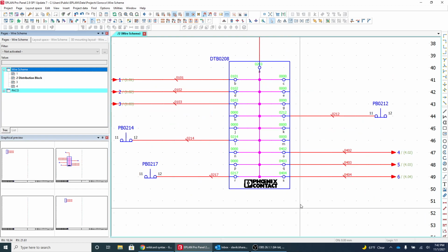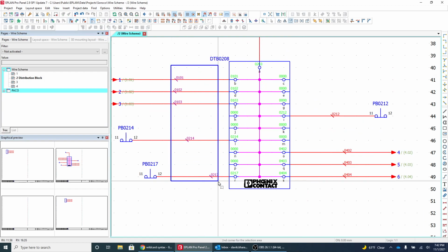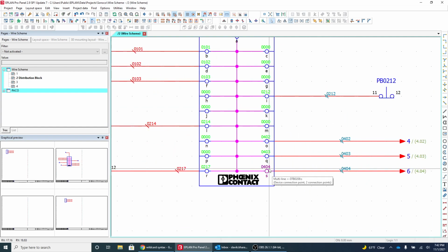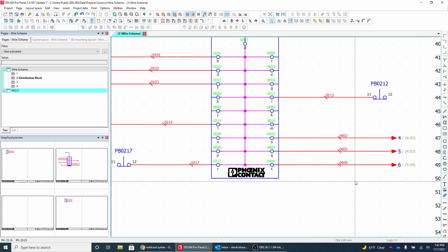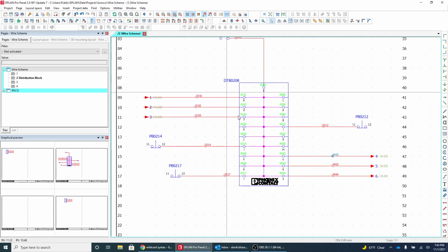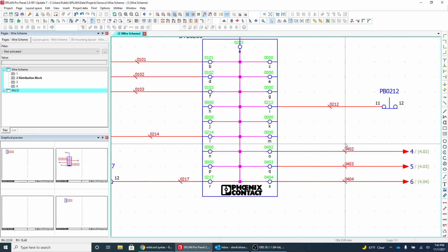All right, let's look at this. So on both sides now, this side and this side, the wire numbers are actually matching what we see in this block property. And we see, for example, these three here, the interruption point is pointed to page 4, row 2, and the wire number is actually based off of that. So this format is forcing these wire numbers to be what's on the other end of these connection definition points, the device connection points. Sorry.